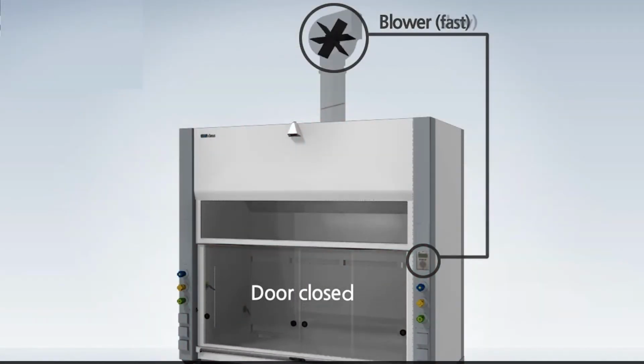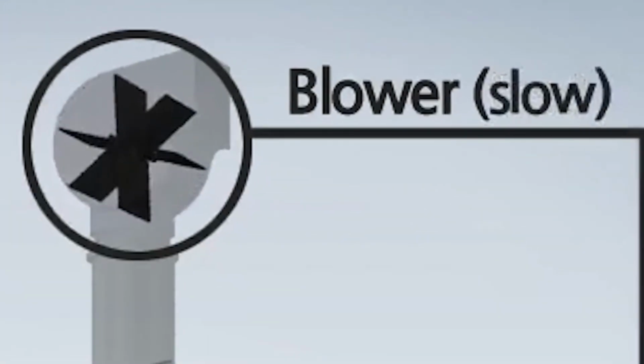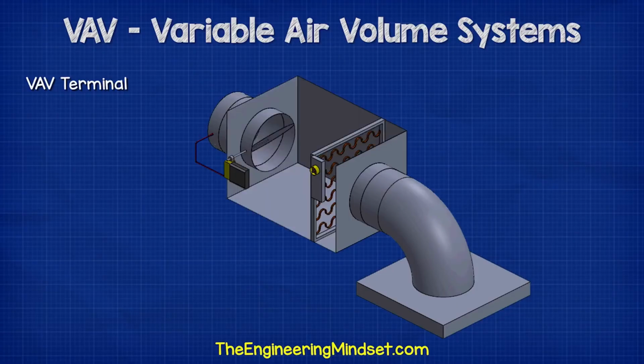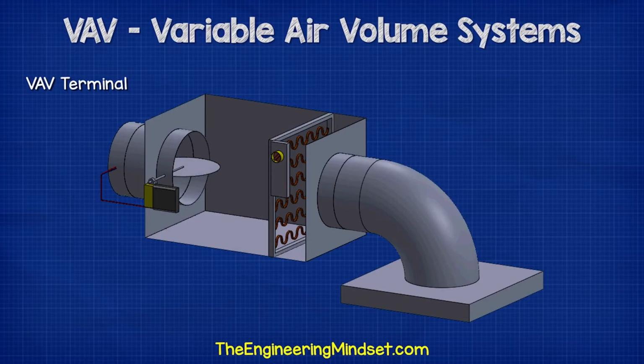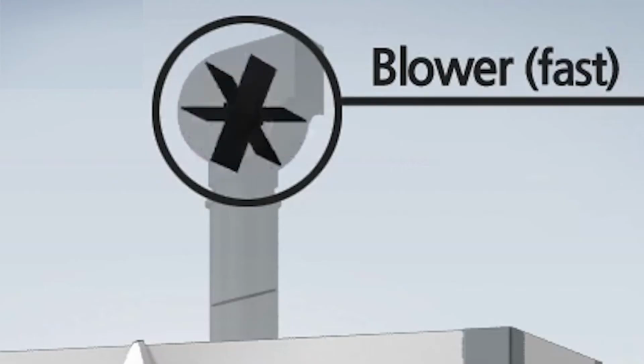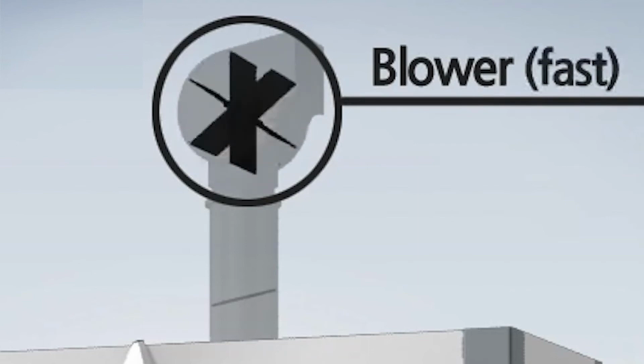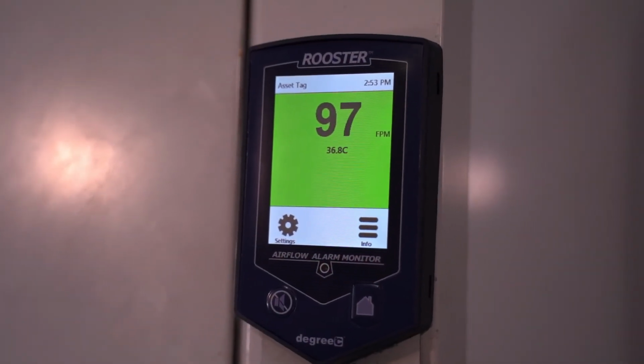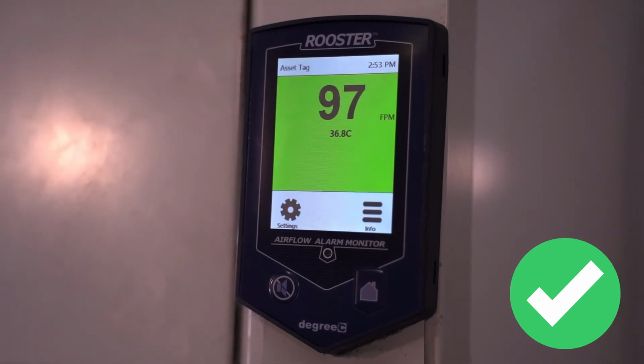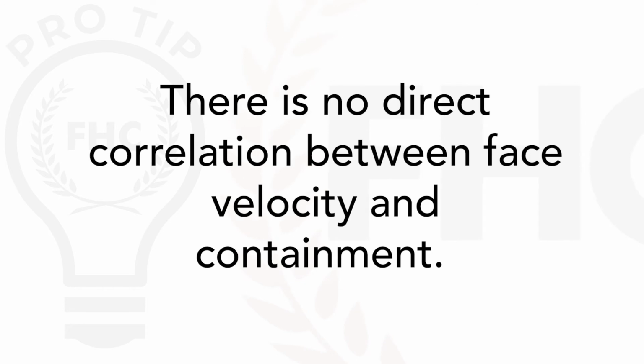Let's say the hood has an experiment running and you have the sash closed. The amount of air the hood is exhausting is low. The room's supply air terminal has closed down to keep the supply air coming in equal to the amount of air the hood's exhausting. Now you open the sash and the exhaust volume suddenly increases. But there's a lag time between when the room controller recognizes this volume or pressure shift and readjusts the supply to get back to a stable condition. During this period of lag and instability, a fume hood is more likely to have a loss of containment due to the differential pressure changes. Yet it is highly possible that the face velocity has remained within an acceptable range. Remember what I said, there's no direct correlation between face velocity and containment.